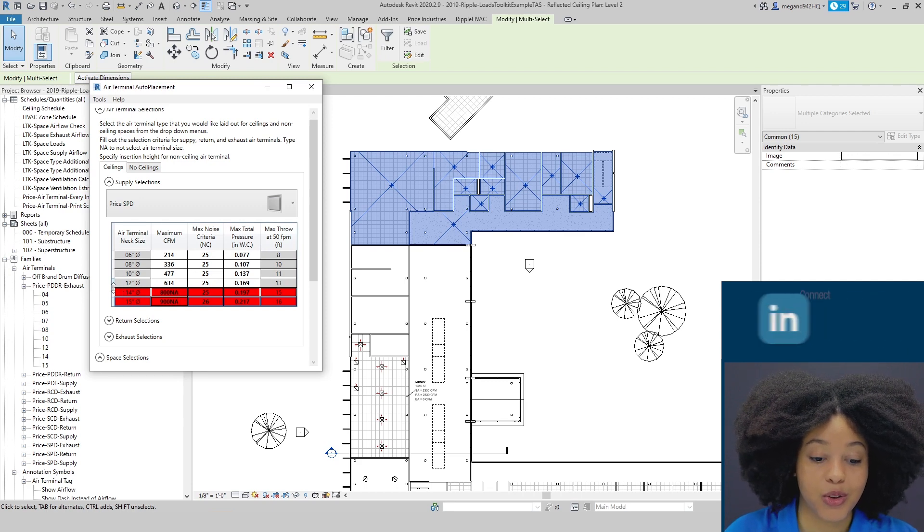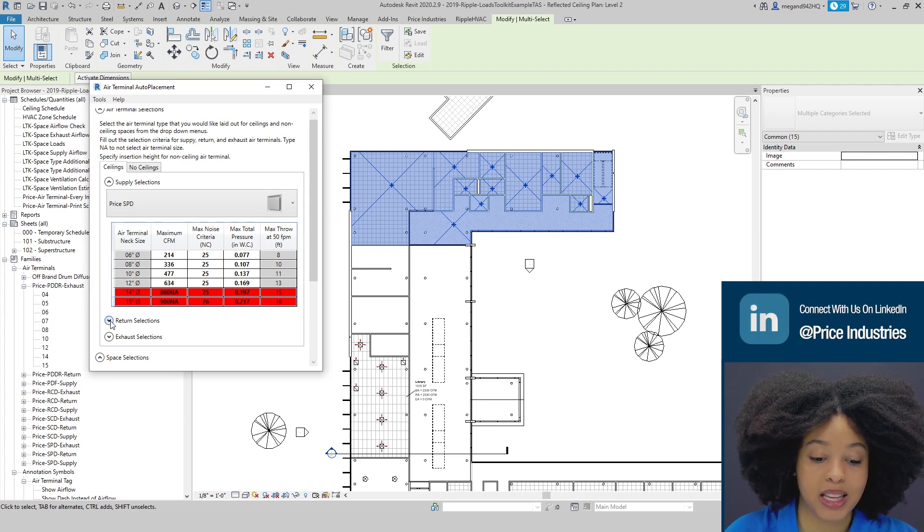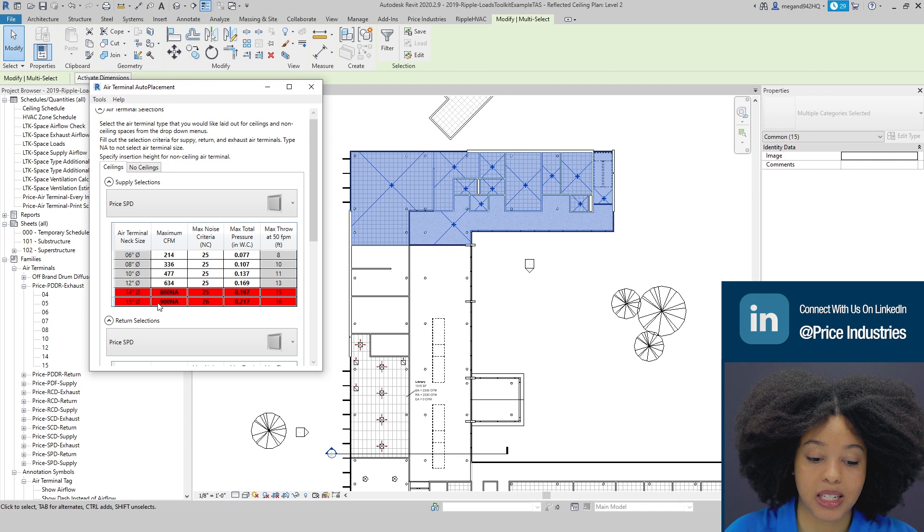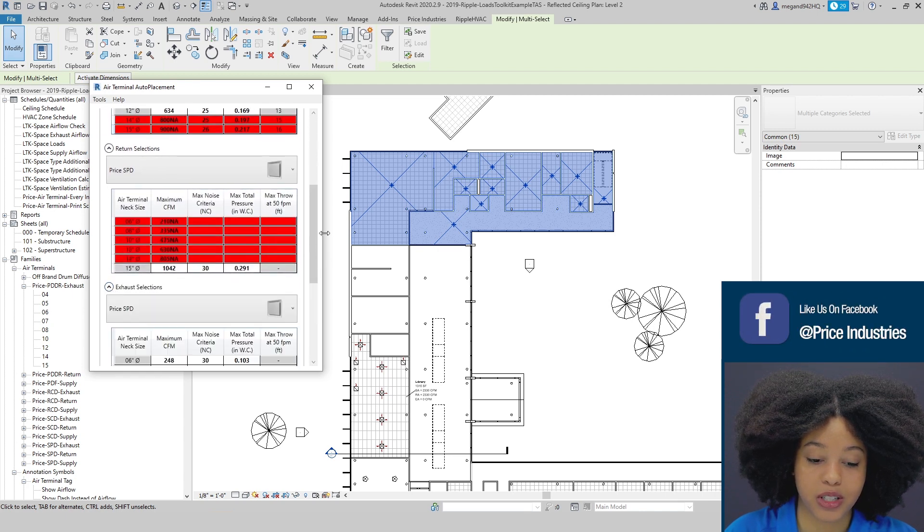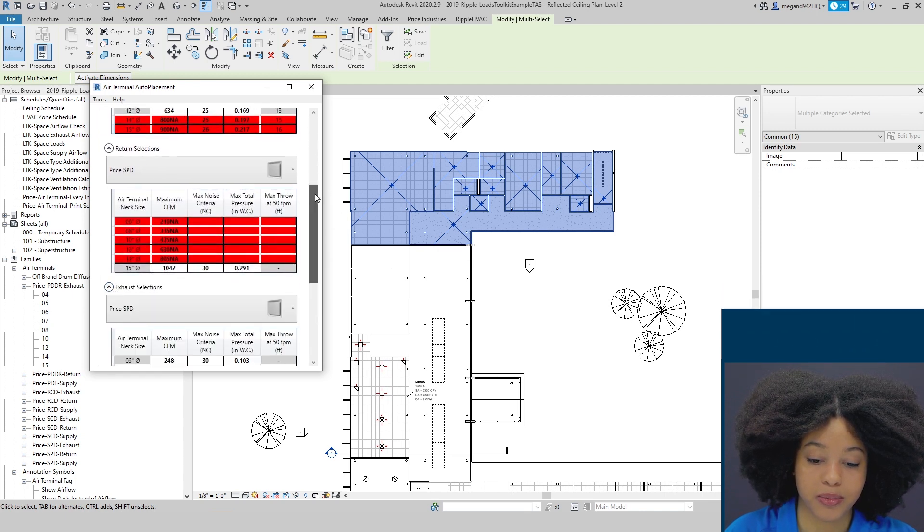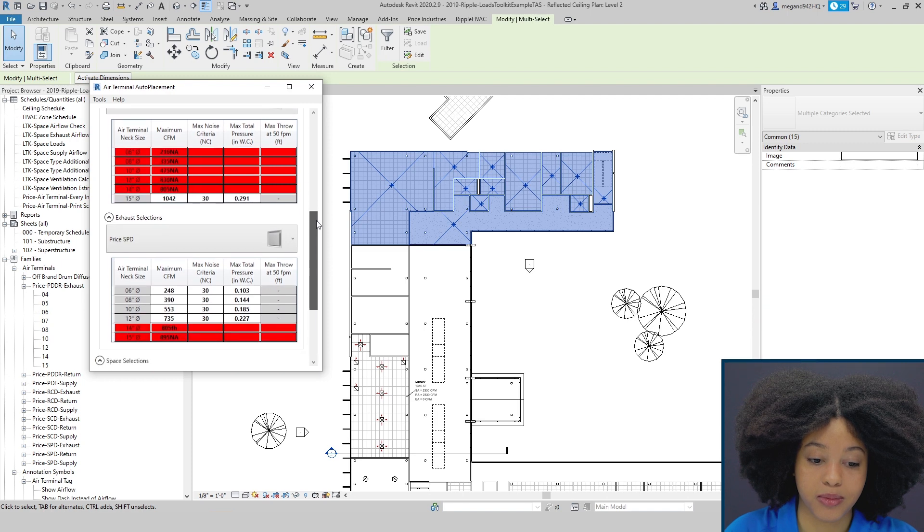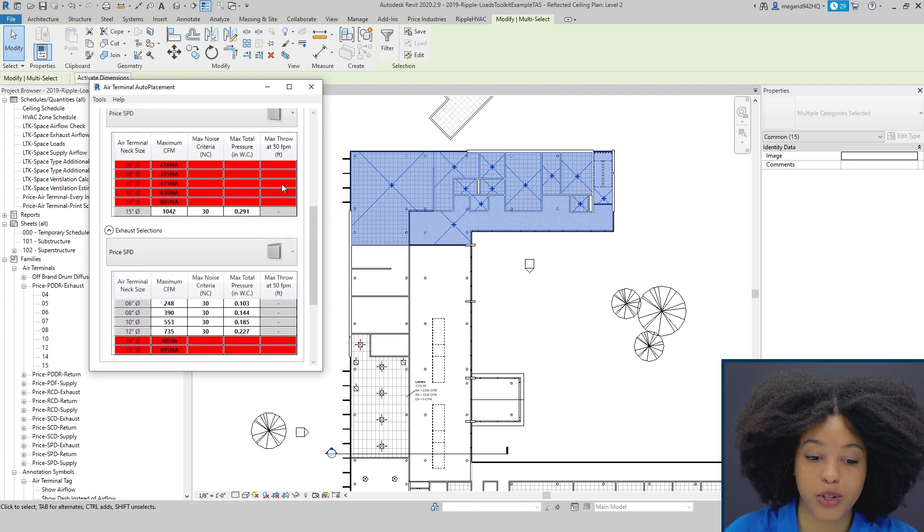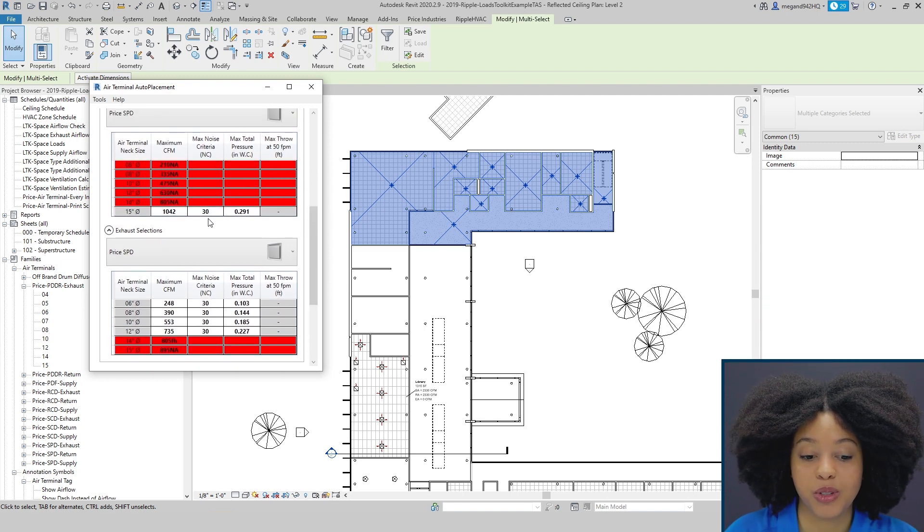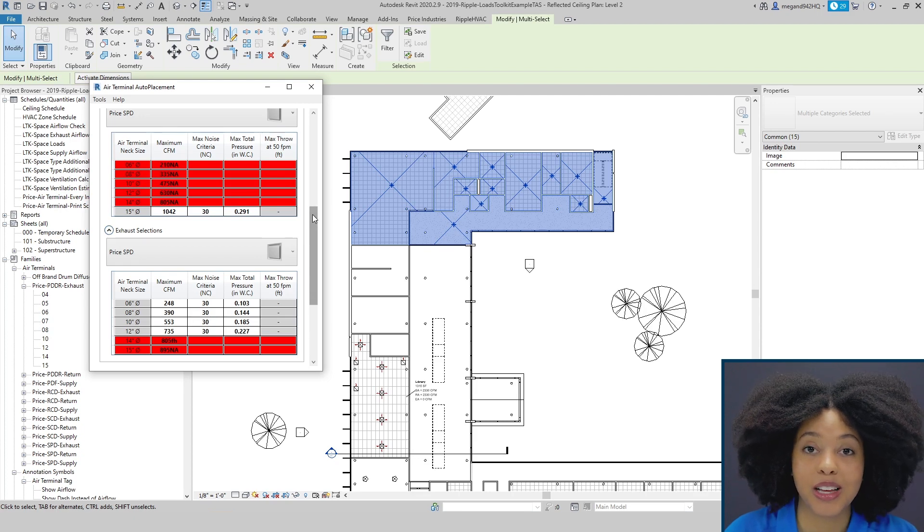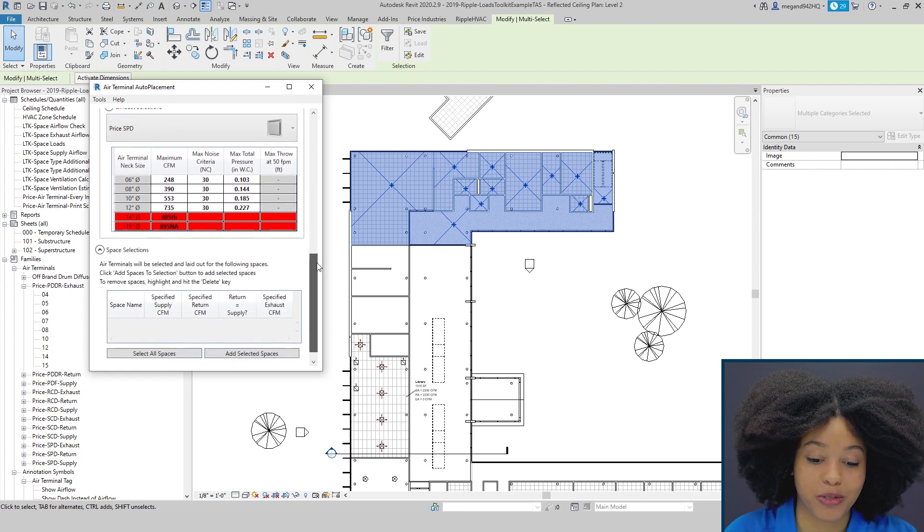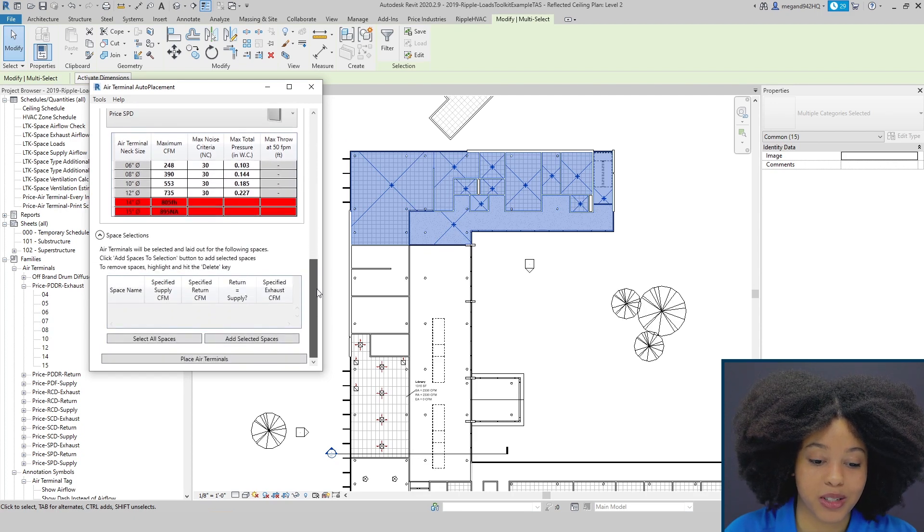Often we don't go above a 12 inch radius due to crowded ceilings. You can make the same type of selections for your returns, as well as for your exhaust. Often for returns, regardless of performance, we often just select the largest size. But this is completely customizable to the preference of the user.